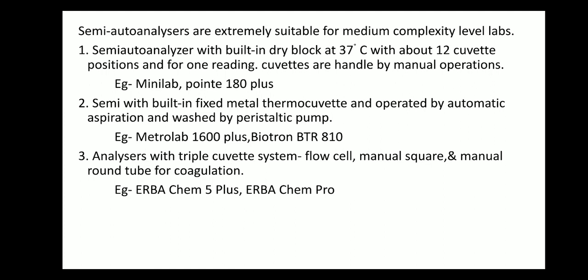The first type has a 37-degree incubation point and it has 12 cuvette positions and one reading cuvette. This we can handle by manual operations. Examples, models for this type of semi analyzer are Minilab, Pointe 180 plus. These are the names of the analyzers.